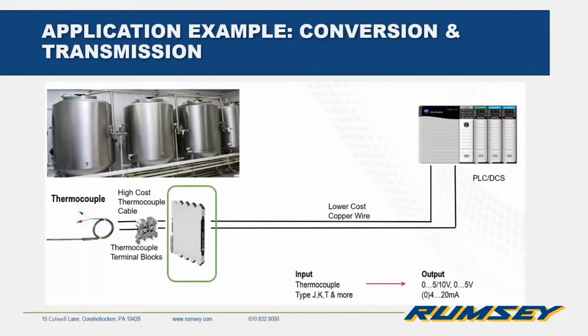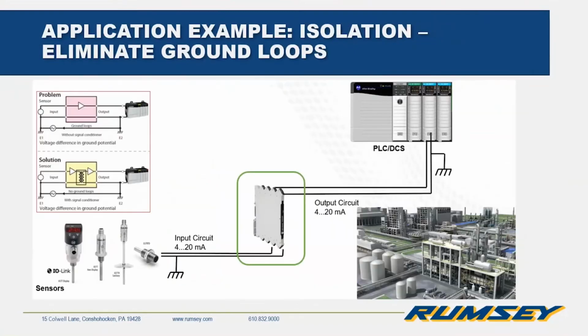And here's an example. I kind of briefly touched on this, but if you had a thermocouple wire going into the signal conditioner, you could then on the output use lower cost copper wire and carry that as either a 0 to 5 or 10 volt signal or a 4 to 20 back to the PLC instead of using a costly thermocouple wire. And the next slide will show how they could eliminate ground loops. So you would take that 4 to 20 into the signal converter and you would make sure it's clean, prevent the PLC or the input card from getting hit with any kind of ground loop that could potentially take it out.